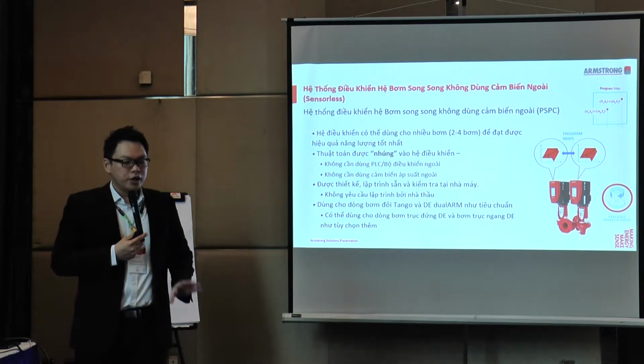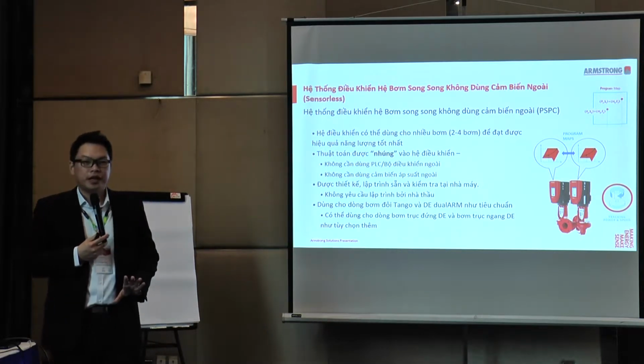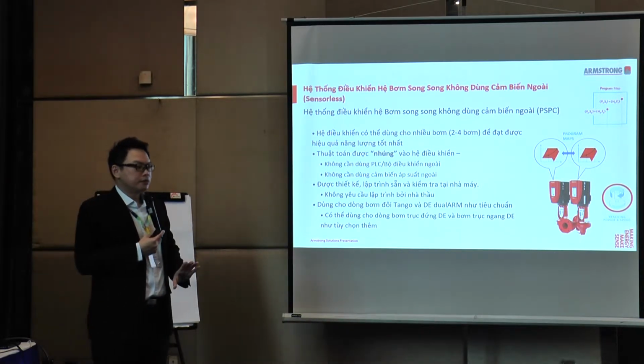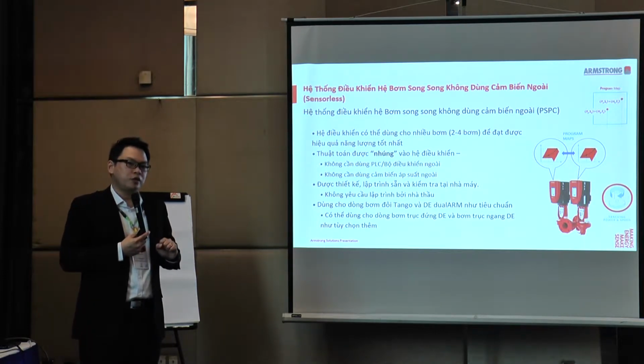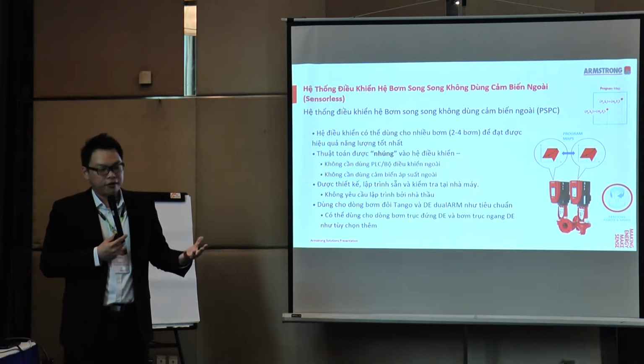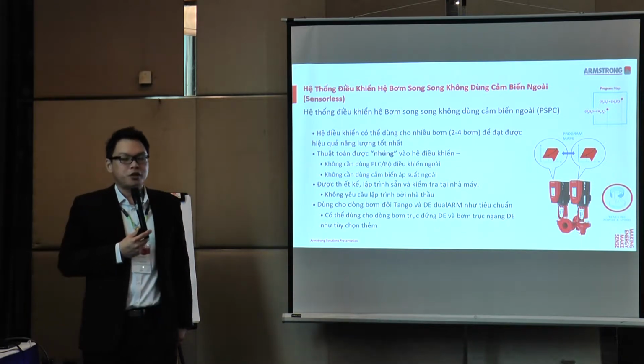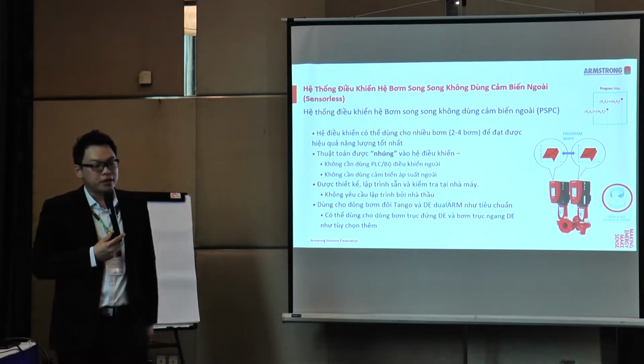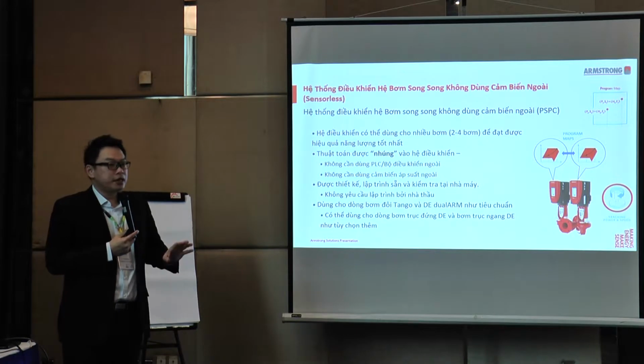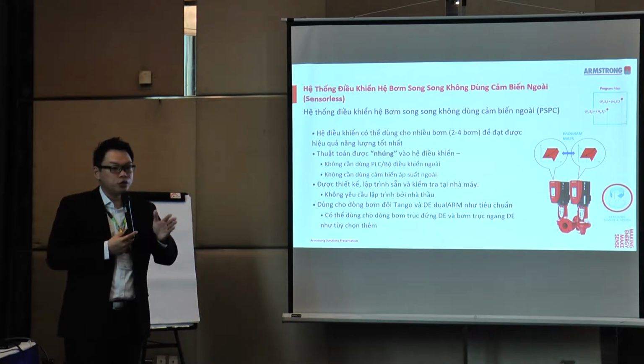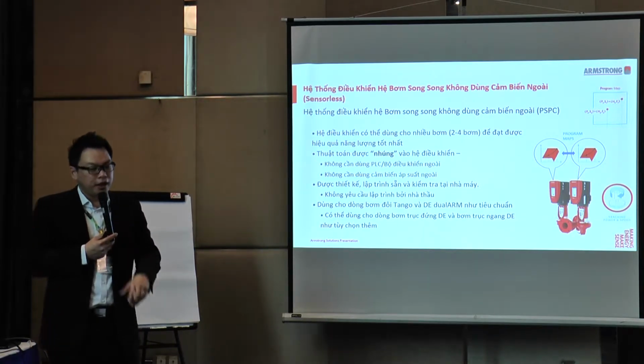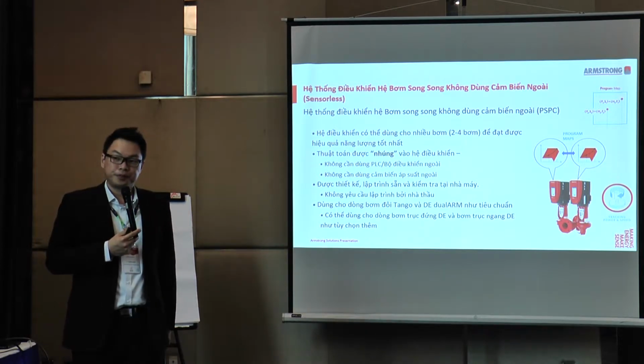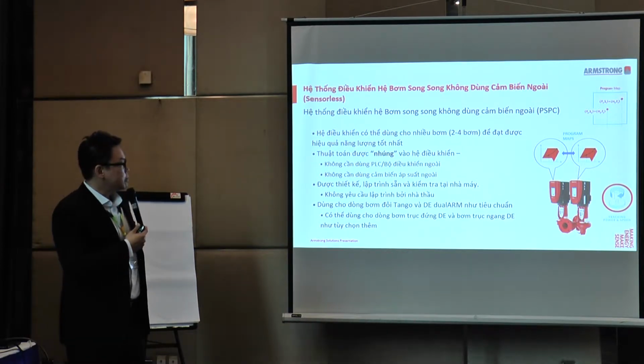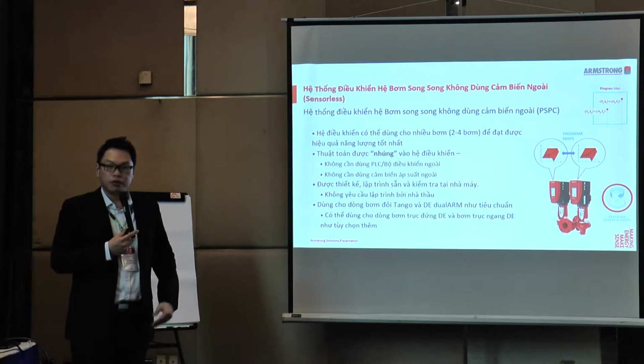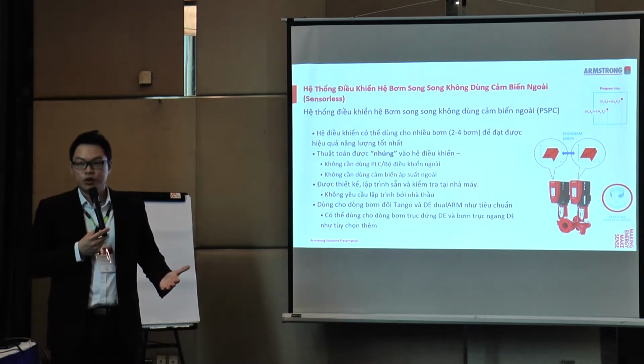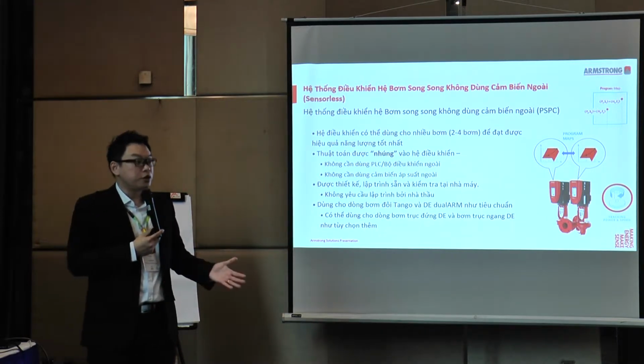Okay. So the beauty of these tango pumps is that they come with our innovative product that we have patented, which is called the PSPC, or Parallel Sensorless Pump Control. It is basically a control logic that controls up to 2 to 4 pumps for best efficiency operation.